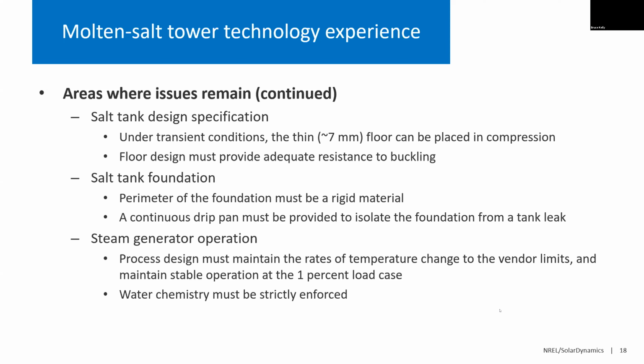The other thing that needs to be done is to control the water chemistry. It sounds like that should be plant O&M 101, and it sort of is, but if the dissolved oxygen levels are too low and the pH is too low, you wind up forming rust in the condensate system that is not adherent, and flow accelerated corrosion will carry these rust components into the evaporator. And in the evaporator, if you're using stainless steel tubes, and several plants have done that, you wind up with deposits in the tubes. And then you wind up with basically pitting corrosion underneath these deposits due to galvanic action in the heat exchanger tubes. And again, you can repair this by plugging tubes, but again, you're suffering downtime on the heat exchangers. And every time you go down for a tube plugging operation, you're out of service for at least a week. And so again, it's important to control water chemistry and basically process conditions on the steam generator to make sure that the steam generator doesn't become the largest availability problem in your project.